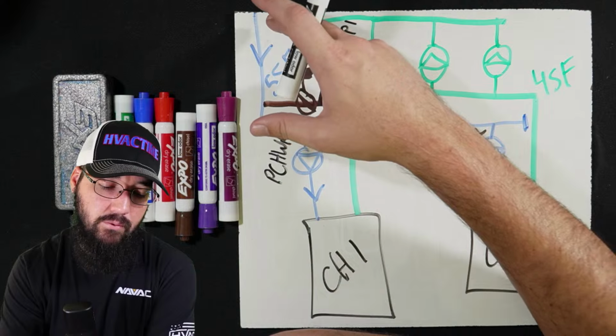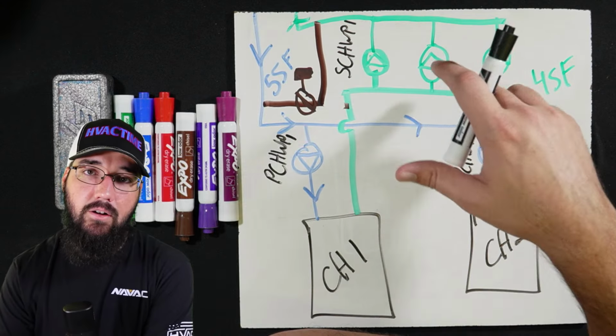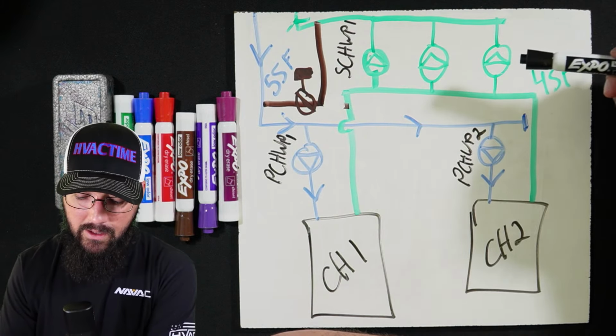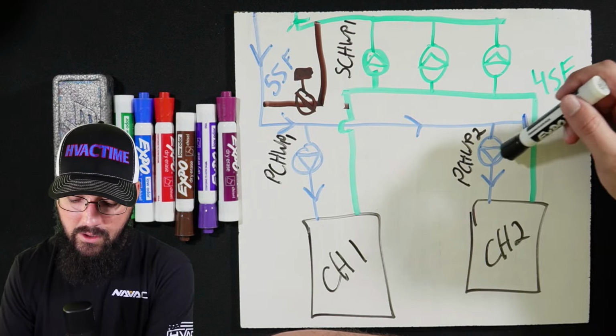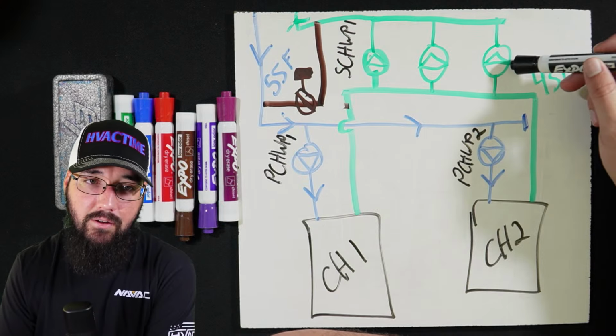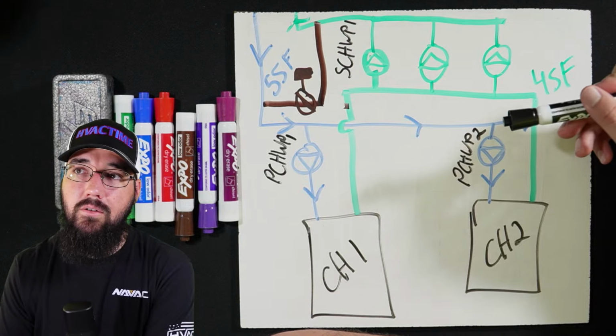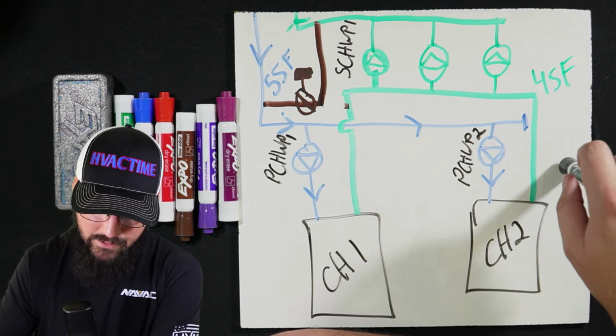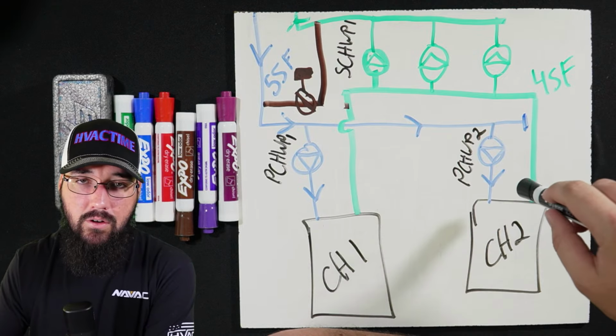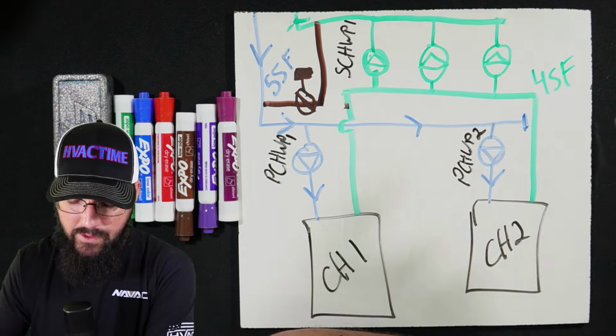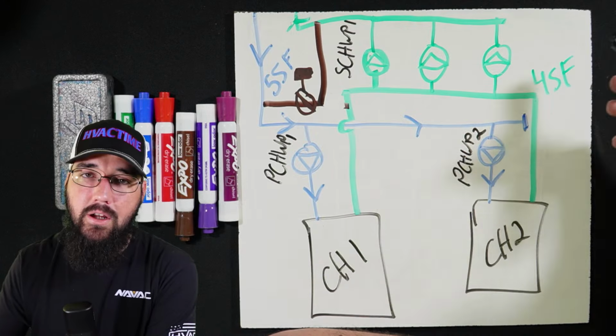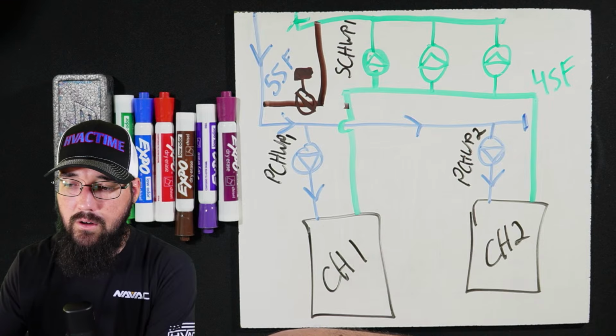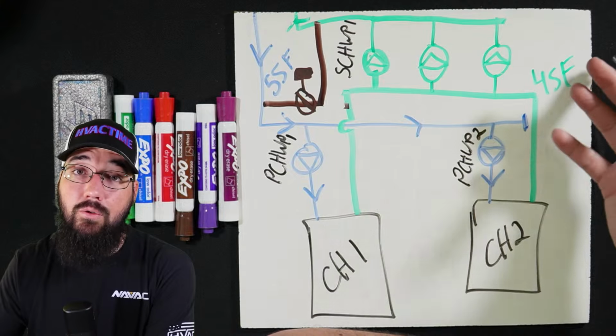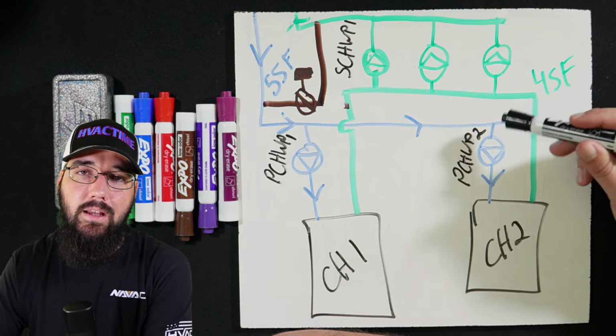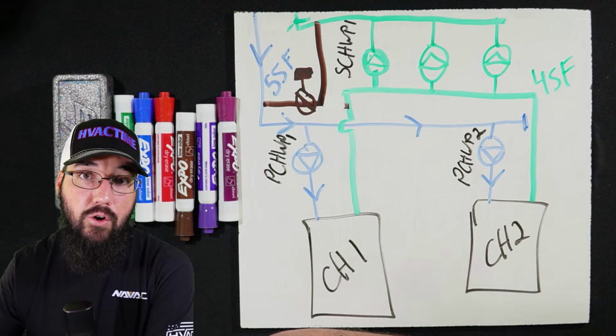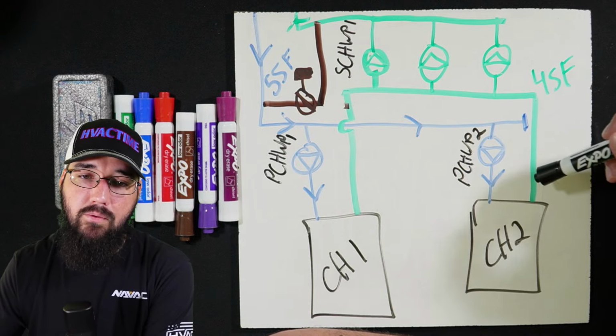The more load we have, the more flow is being asked for, the more we need to turn on the secondaries to give that side of the system that flow. And all this will need to turn on simultaneously. We should not be running the primary pumps without having the secondary pumps on. And this is part of where the staging sequence on a plant as a whole, typically, when we're first turning a plant on, whether it be from being off overnight or whatever the case may be, maybe we had a temporary shutdown on the manufacturing line, and we just shut the loop down because we didn't have any load and we need to bring it back up. We'll turn these pumps on usually and establish flow for 10, 20, 30 minutes, and make sure everything balances on the water side before we ever ask the chiller to actually turn on.